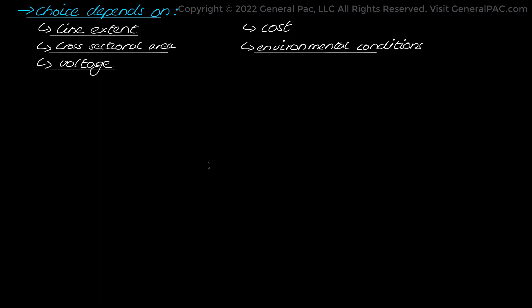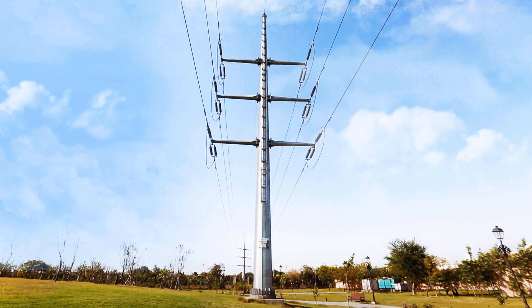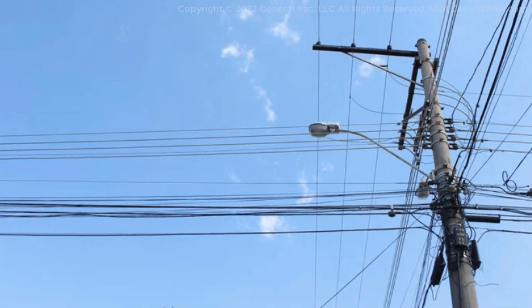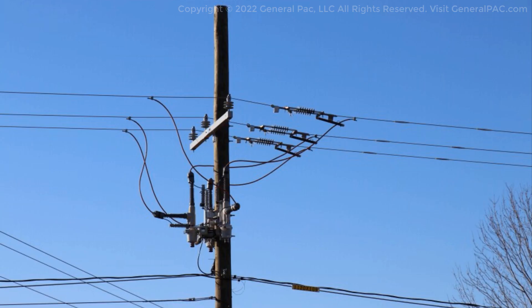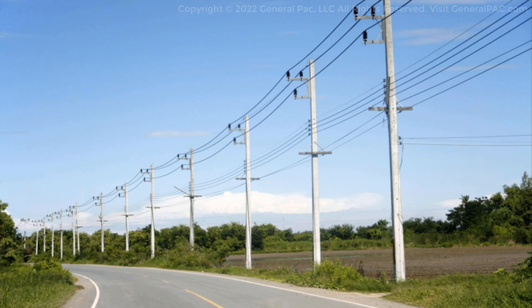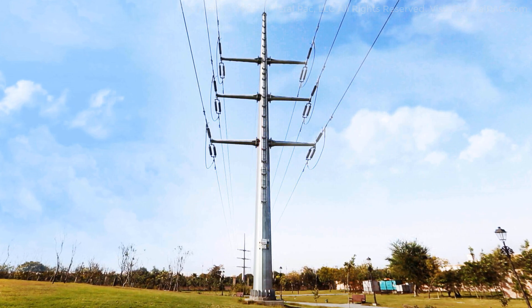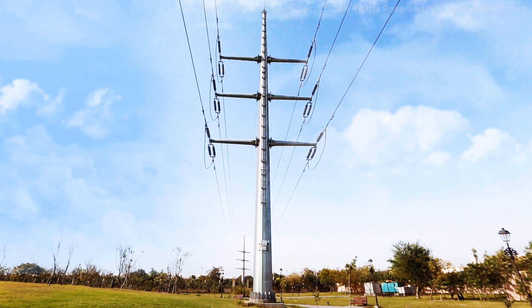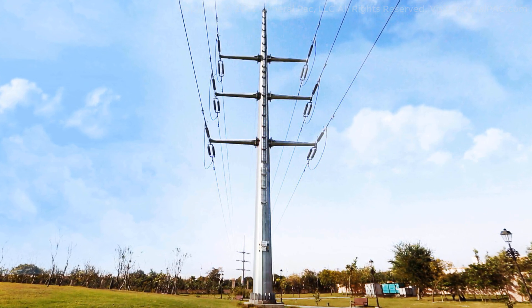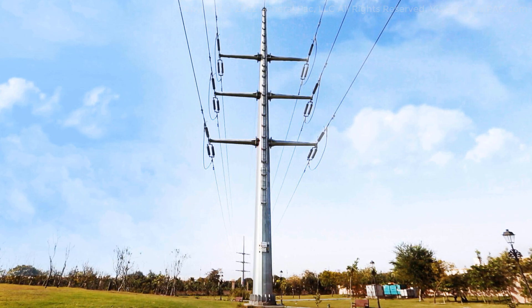For long-distance transmission purposes, steel towers are employed, while wooden poles, steel poles, and reinforced concrete poles are used in cities for low voltage secondary distribution. Steel towers can be up to 50 meters high and be placed among great spans of almost 370 to 460 meters.